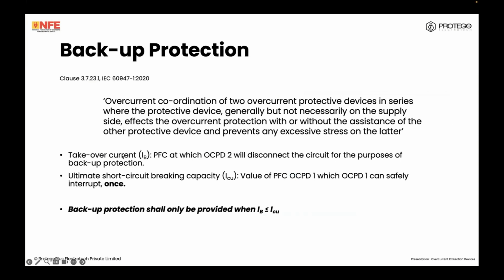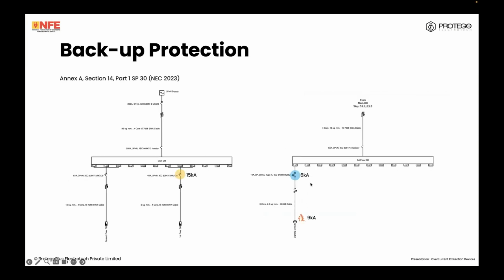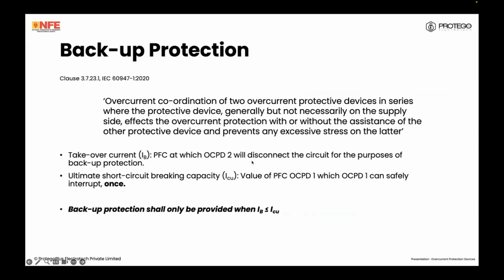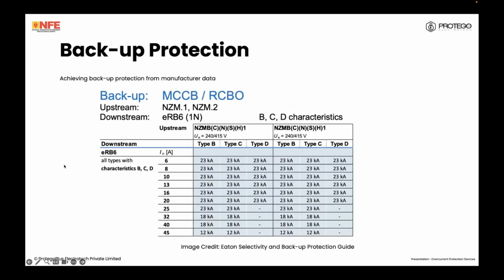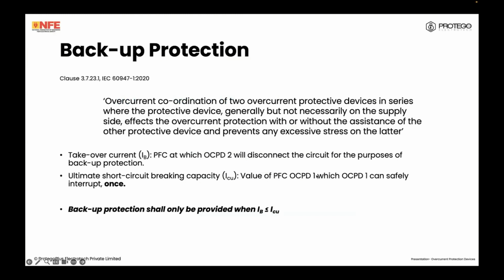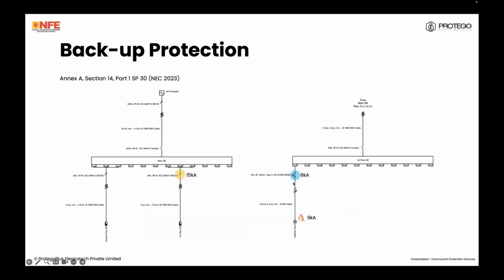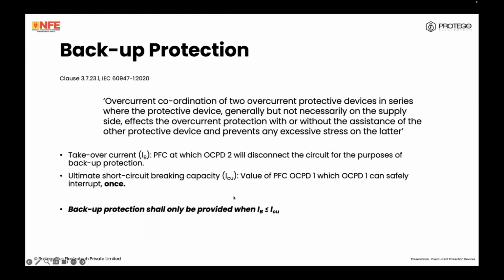Now, for backup protection, we have something called a takeover current, which means for faults of a certain current seen by this OCPD, this will step in and help clear the fault. That's simply the takeover current: the prospective fault current at which OCPD will disconnect the circuit for the purposes of backup protection. And then you've got the ultimate short circuit breaking capacity of OCPD1. This is the value of prospective fault current which OCPD1 can safely disconnect. Obviously, backup protection shall only be provided when the takeover current is lesser than or equal to Icu, because we do not want a situation where this is only taking over, say, when this reaches 8 kiloamperes. Then this is going to have an arc, this is going to be messed up, and you're going to have a lot of damage to your system. Just keep that in mind.